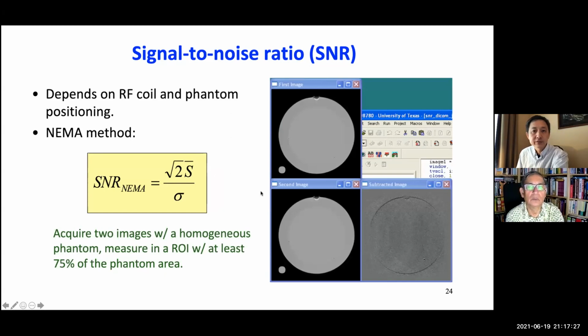Okay, the next is a very important test. That's the SNR, signal to noise ratio. Signal to noise ratio would depend on the RF coil. So different RF coils are different, and also phantom positioning is different. So when we make the measurement, we want to make sure the phantom positioning and the phantom used are consistent.